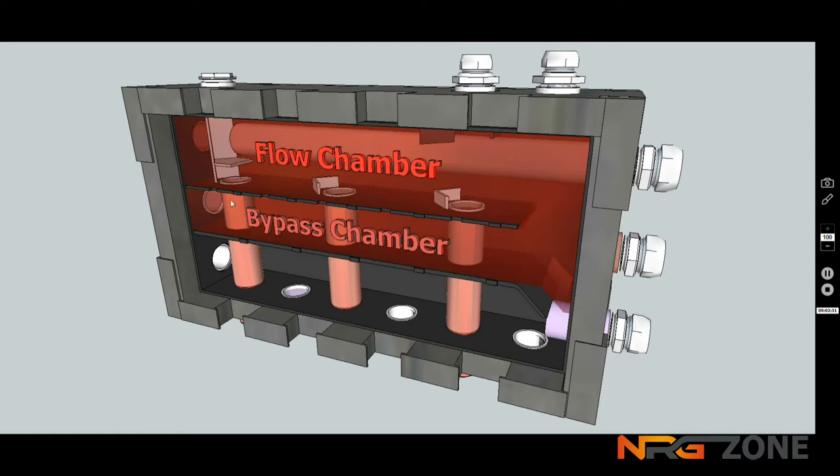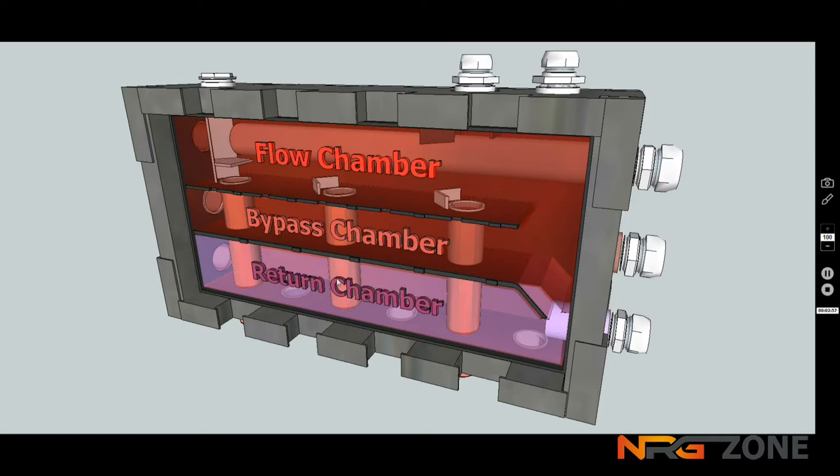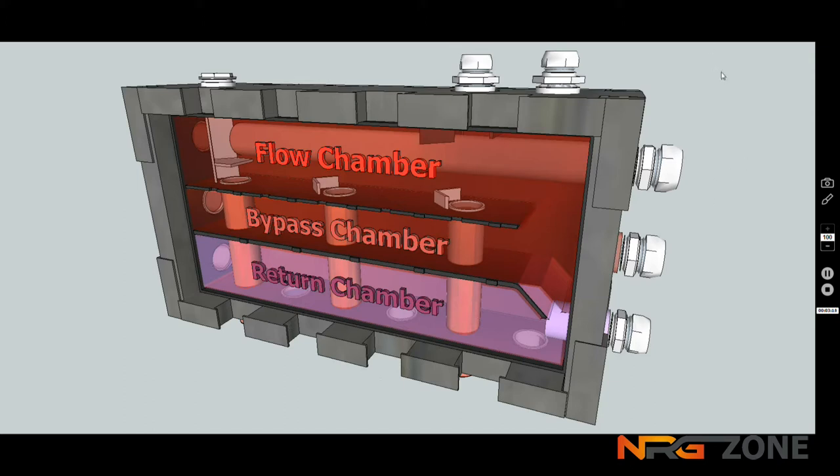So, if heat is drawn away by any given zone, say zone two, and it arrives back in on its return port, then of course, the return port will fill the return chamber with the coldest possible water. This water is what's perfectly required for a condensing boiler to condense, or for a heat pump to work properly. So, this unique opportunity provides the system with an opportunity to have high temperature from a solid fuel stove, delivering back to high temperature solid fuel return, and also taking the zone return, and offering that primarily back to the condensing boiler. So, it makes the creation of that system extremely simple, as I'm sure you'll soon see.